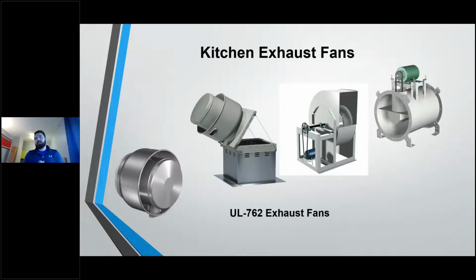Moving on to the next part of the kitchen ventilation system, it's a UL. So when we're talking grease exhaust, we're talking a UL 762 exhaust fan. So that UL 762 is the rating of the motor. It's removing the motor from the airstream, from the grease exhaust airstream. And then from there, it's just whatever configuration you're going to utilize. So sidewall termination exhaust fans are an option.